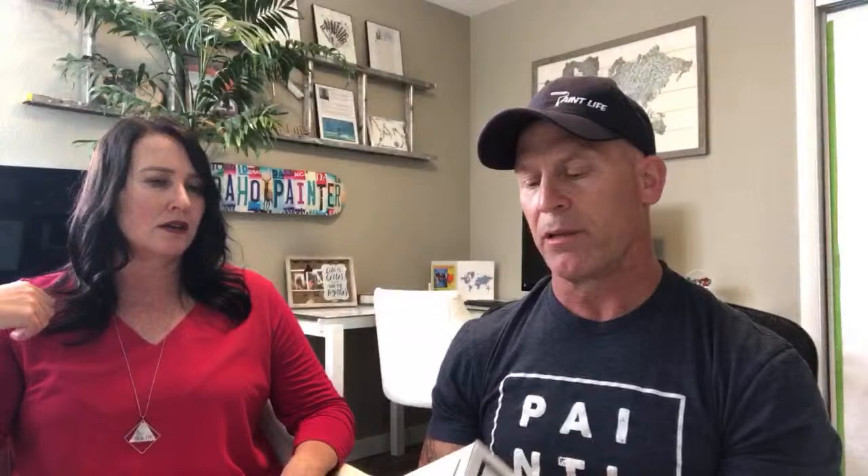Someone in the chat did the math: 8x8 booth = 64 square feet × 100 = 6400 CFM total. This tells you what velocity your fan is achieving. If your fan isn't performing, you'll know. The device is made by Dwyer Instruments in Michigan City. I'll find out from Kyle how much it costs and where he bought it - you can also go right to the source since there's a phone number on it.